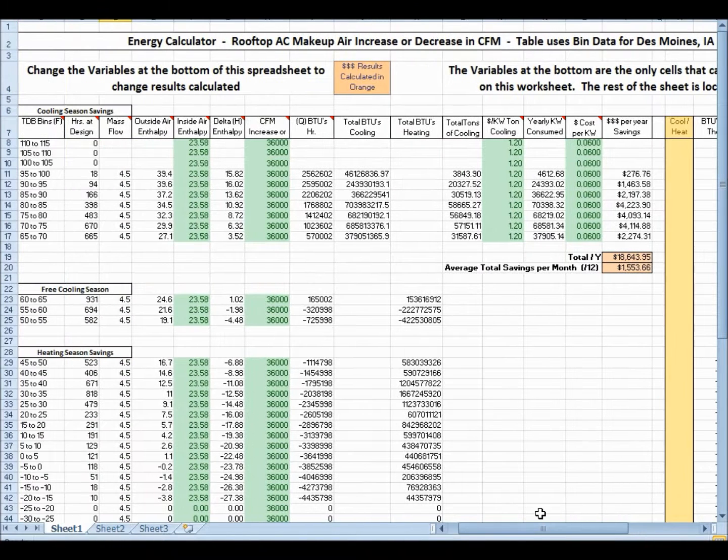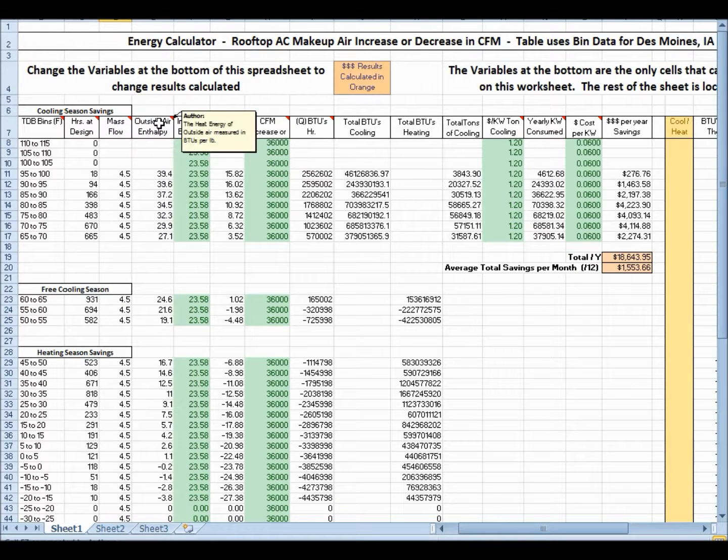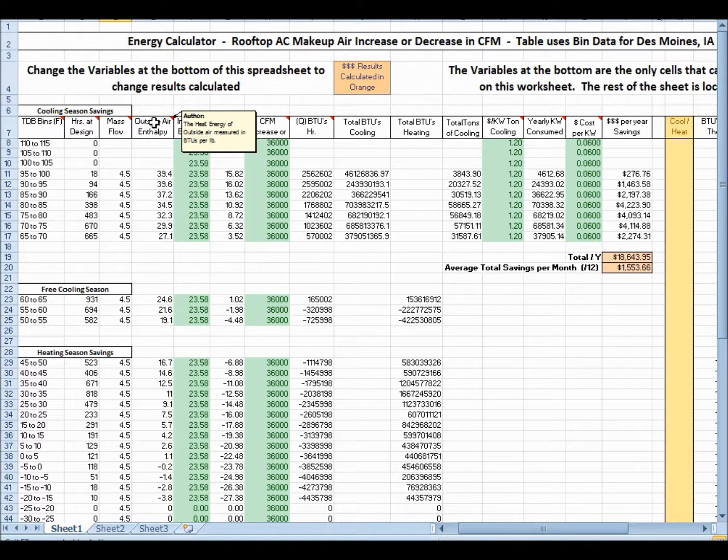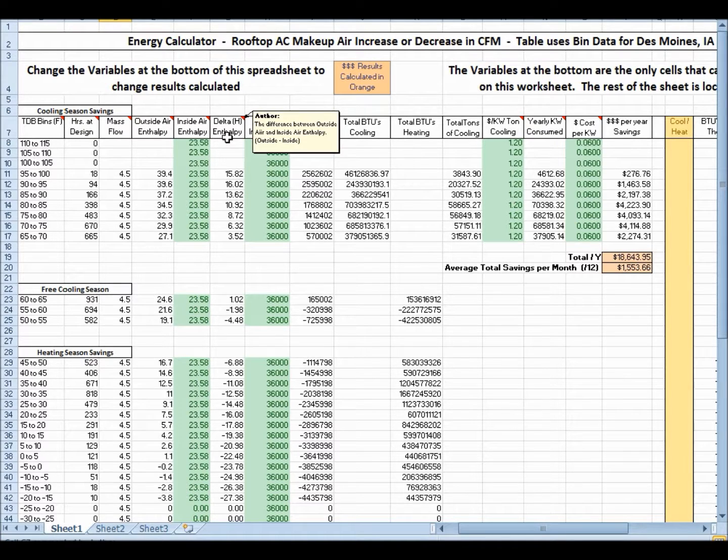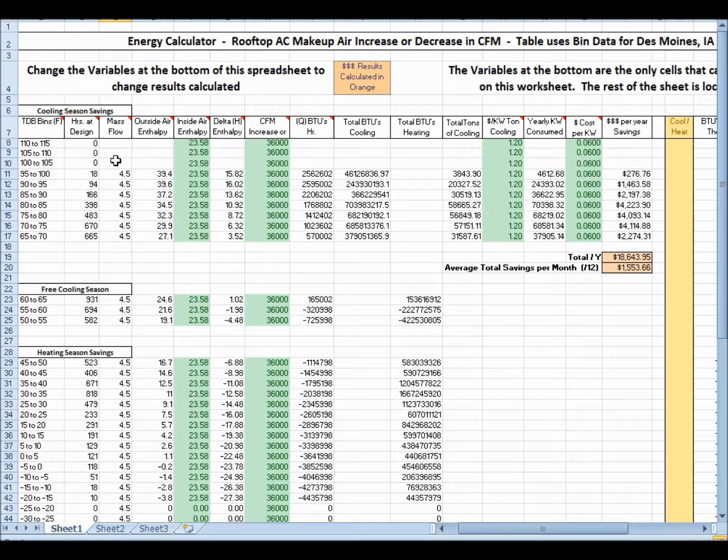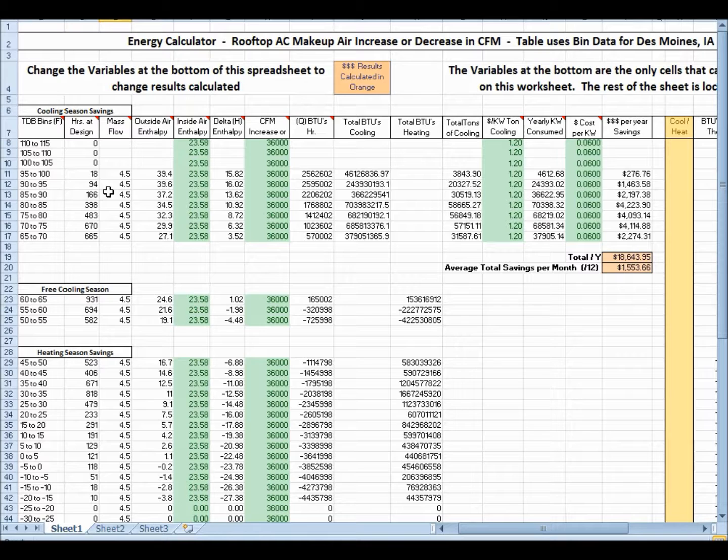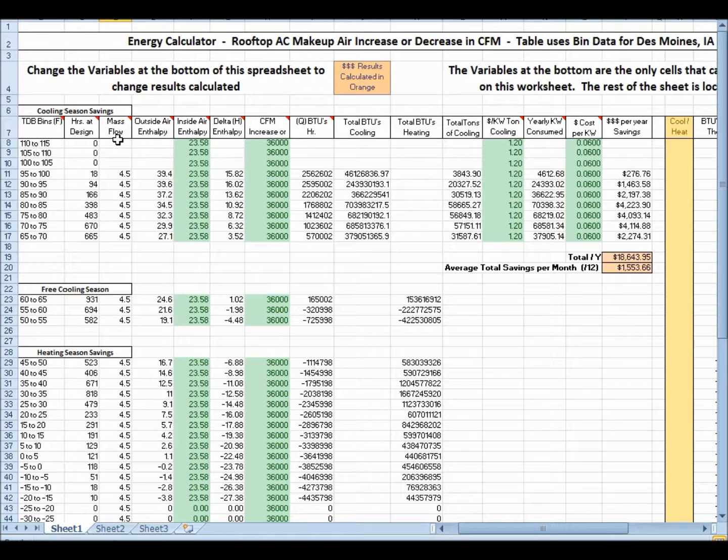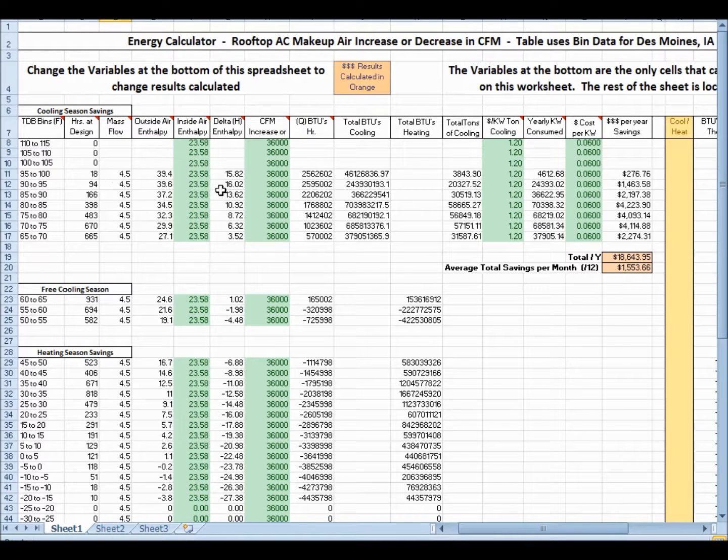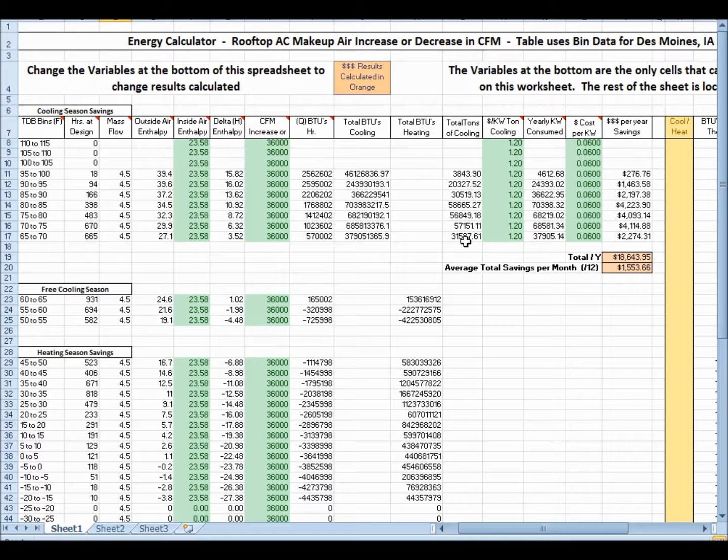The difficult ones are this mass flow here, enthalpy and delta enthalpy. Enthalpy is just the heat per pound. So, air has a weight. Air weighs something, and a pound of air has an enthalpy of this, and it has certain values that you can use to calculate how much heating or cooling is needed. Now, that's not a great explanation, but you can read these, and that's where this 4.5 comes in. This is really what's called a constant. It's mass flow of the air. So, this constant is what does a lot of the calculations that come up with total BTUs, total tons, et cetera. So, that's that.